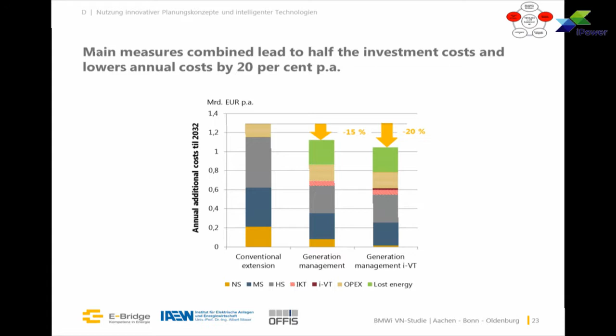It's not that they just add up - with conventional extension we have up to 1.3 billion euro per year in additional costs. Then with generation management, as I mentioned earlier, we have about a 50% cut, and if we combine it with all the individual costs for the intelligent voltage transformer, we have an additional 5% cost but might save 20% in annual costs on the grid extension needed.